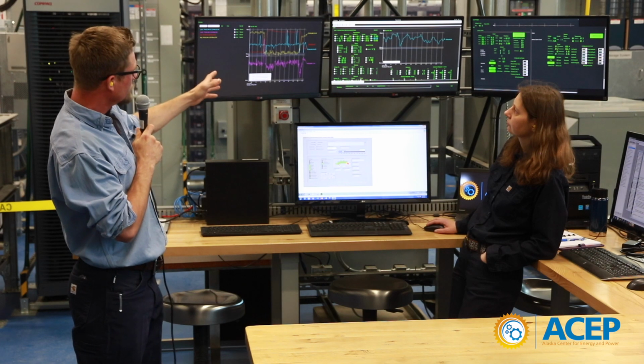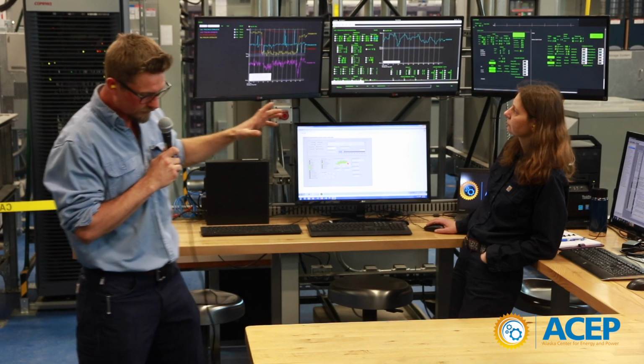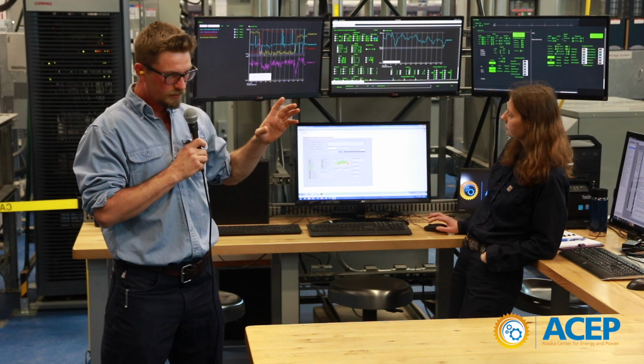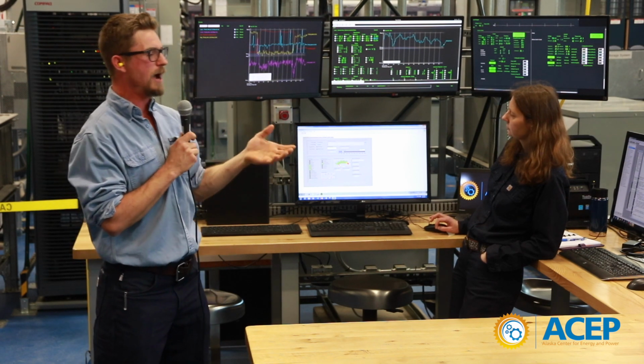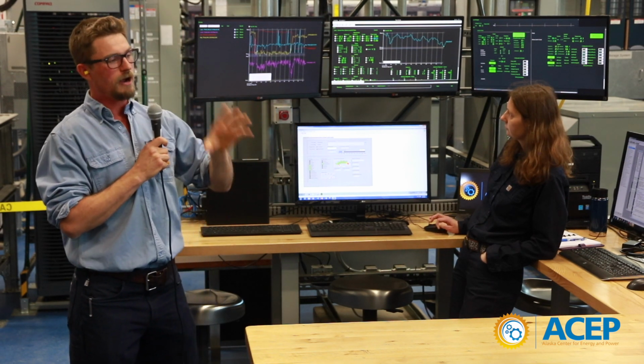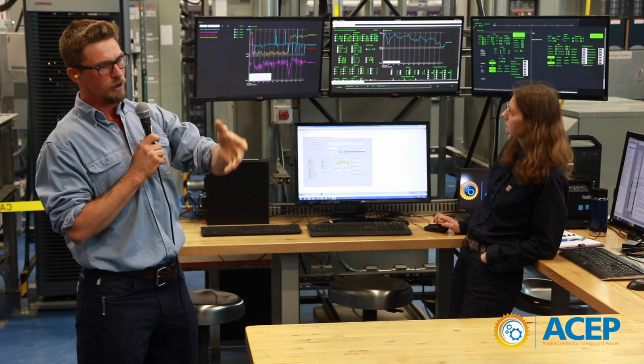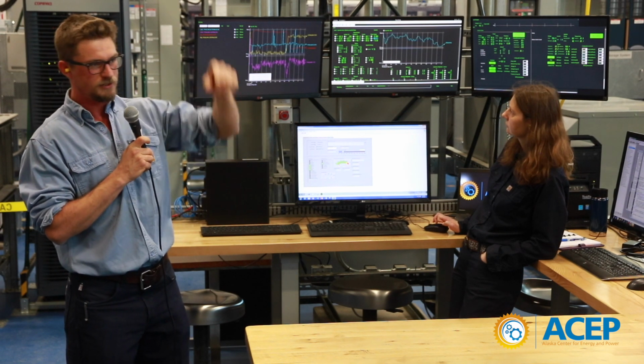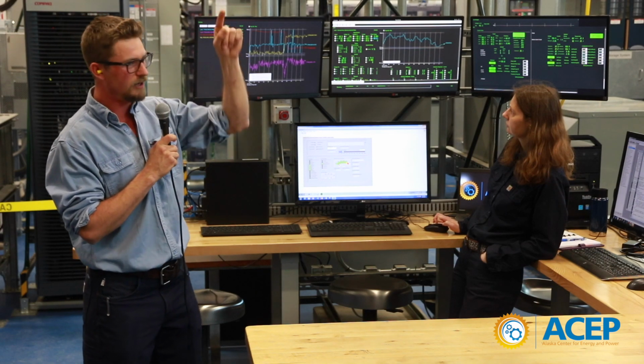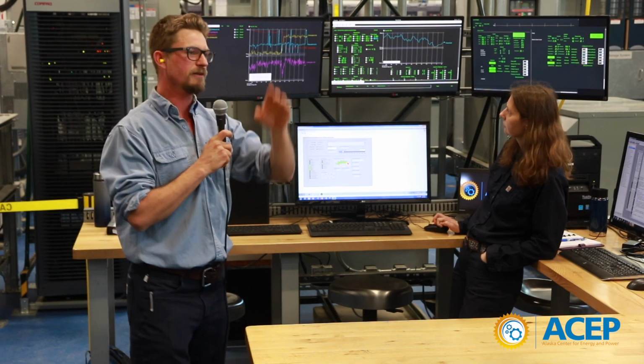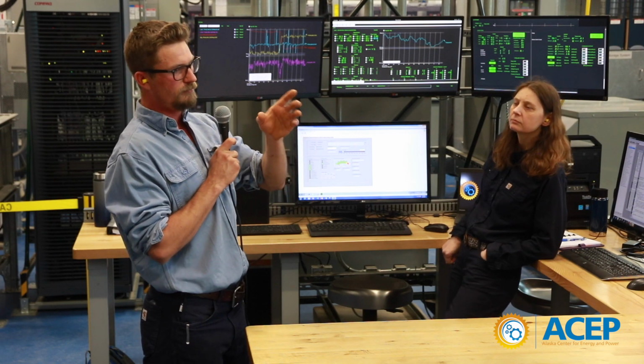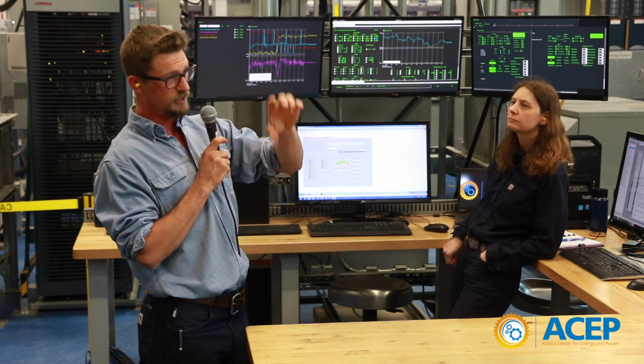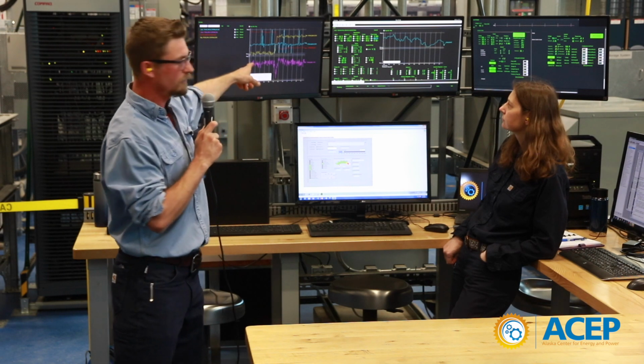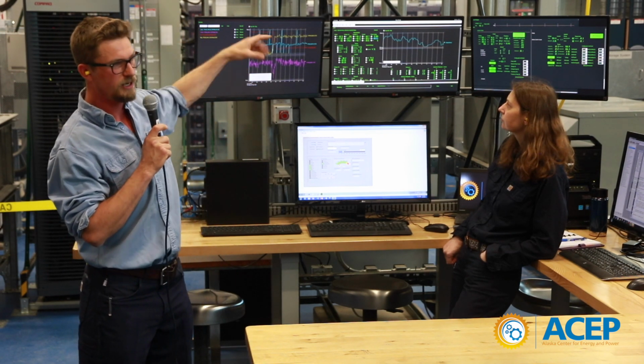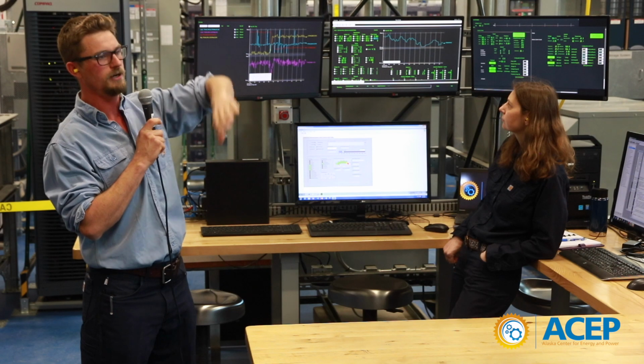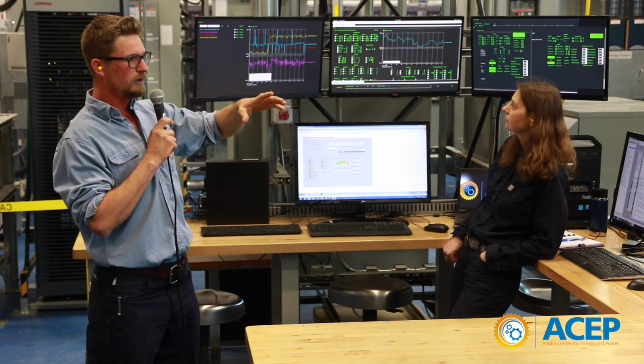Right now, the battery is helping improve our power quality, because our power quality wasn't as good once we added all that wind power to the grid. The wind power is ramping the system up and down, and the generator is having a harder time maintaining our frequency within acceptable bounds. Now that we've put this inverter and battery on the grid, it's helping the generator maintain our system frequency, which is great.